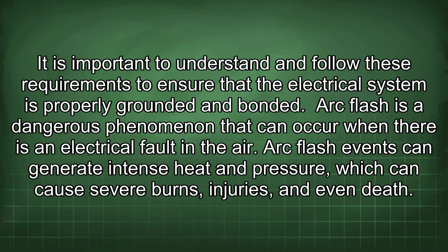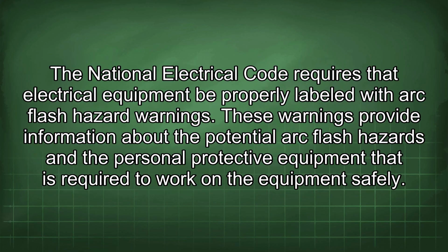Arc flash is a dangerous phenomenon that can occur when there is an electrical fault in the air. Arc flash events can generate intense heat and pressure, which can cause severe burns, injuries, and even death. The National Electrical Code requires that electrical equipment be properly labeled with arc flash hazard warnings. These warnings provide information about the potential arc flash hazards and the personal protective equipment that is required to work on the equipment safely.